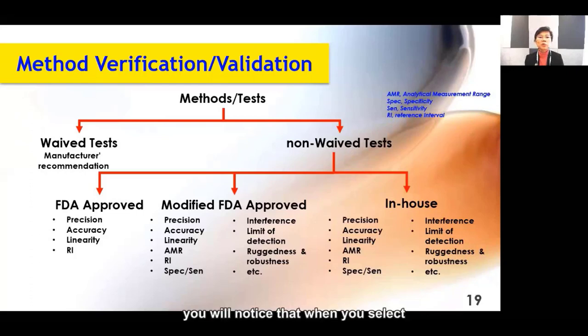However, in this example, you will notice that when you select or you already have the method that you want to implement in your laboratory, you should classify your test as waived test and non-waived test. A waived test is a test that is easy to perform, easy to run, and has little effect on the patient. A good example of a waived test is a glucose meter. And what you should do for the method verification for a waived test is follow the manufacturer's recommendation.